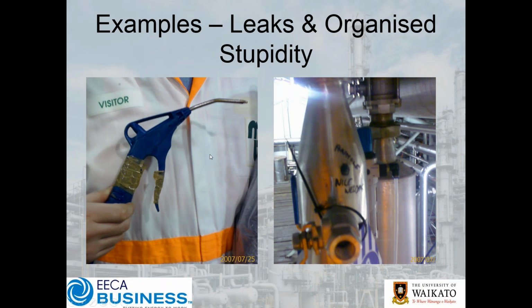Here's another really good example. You see these little dusters, and this particular one had been taped permanently open and on. Of course, just a really, really bad application. Another one here had a pinhole leak in a manifold that had been welded, and a number of people actually took the time to mark it up and poke fun at the poor old welder, but no one took the time to do anything about fixing it. So sometimes it's deliberate, other times our attitudes are as much the problem. Yes, someone mucked up, but who's going to do something about fixing the problem?